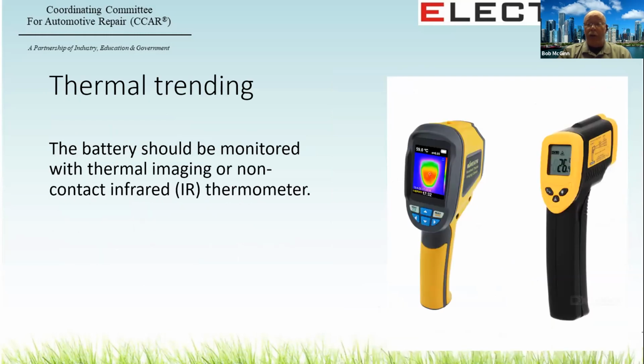The battery should be monitored with thermal imaging or a non-contact infrared thermometer for a sufficient period of time to determine if the battery is getting hotter or cooler over time. Once it has been determined that the battery temperature is trending towards cooler or at stable ambient, then it's possible to address further repair operations. Getting warmer above ambient is not a good thing.